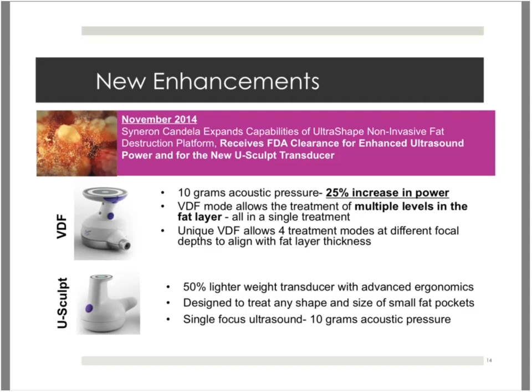So now, rather than doing a single focus deep mode, which we originally came out with, at a depth of 1.5 centimeters, and which is used to treat fat layers greater than 2.5 centimeters, you can now even treat more superficial fat layers at 1.2 and 1.3 centimeters using a different mode called the double focus deep and medium mode. And these are going to be great. We use this a lot for fat layers that are greater than 3 centimeters and for treating large areas that have a lot of fat, like the thigh. Now, if you want to get a really aggressive treatment, the best one, I call this the Mac Daddy treatment, really, this is the super mode double pass. And that's an option in which the first pass delivers energy to a depth of 1.5 centimeters, and in the second pass, you will actually treat 1.2 and 1.3 centimeters of depth.